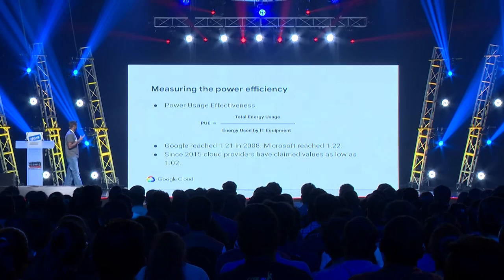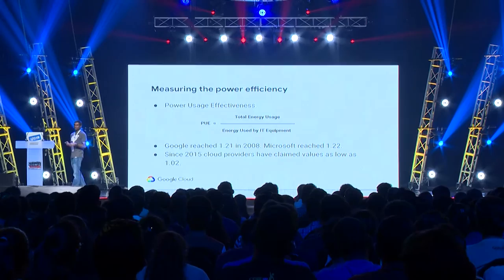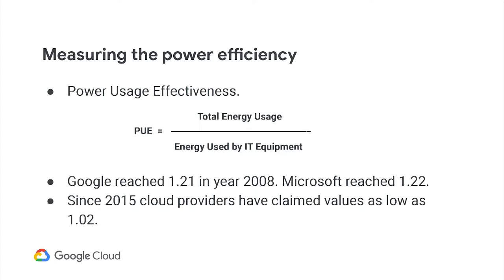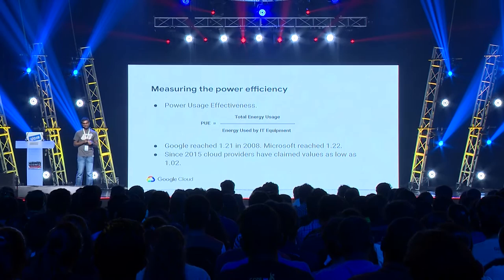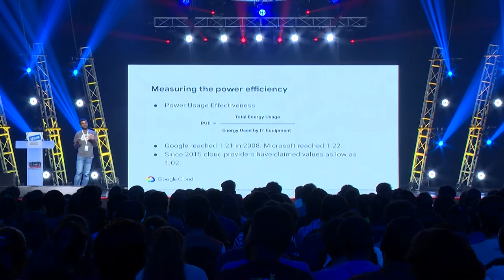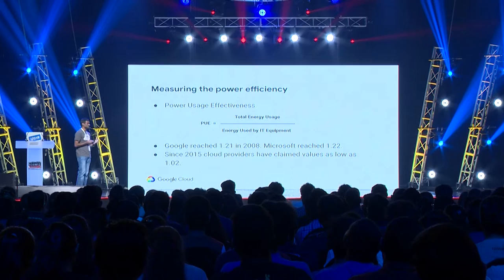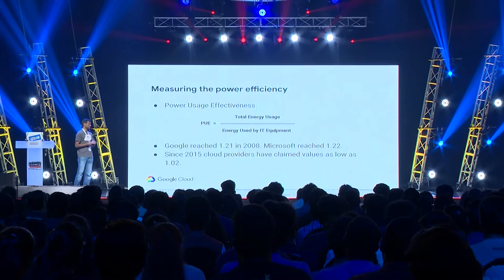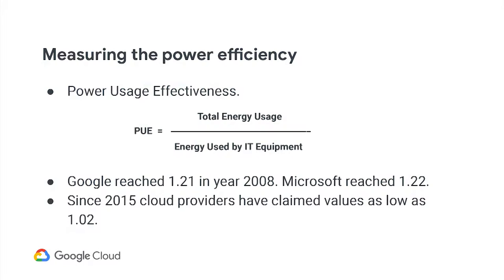How do you measure power efficiency? The most popular metric is PUE — Power Usage Effectiveness — the ratio between the total energy intake of the data center and the energy spent on IT equipment. Ideally this ratio is 1, but in reality you must also spend energy on cooling, so the actual PUE is higher than 1. About 10 years ago, a PUE around 2 was considered good — the gold standard. In 2008, Google made a breakthrough by reaching 1.21, and Microsoft reached 1.22 around the same time. These days, cloud providers report values as low as 1.02.